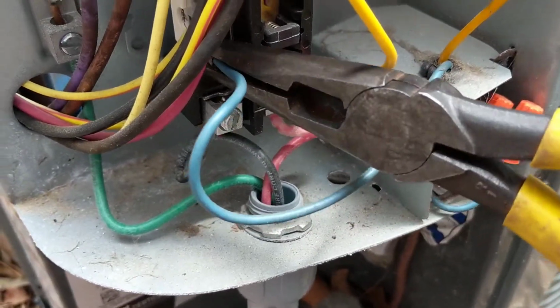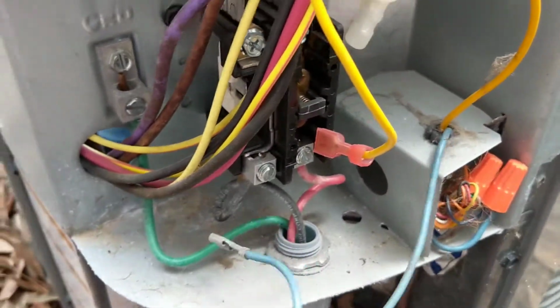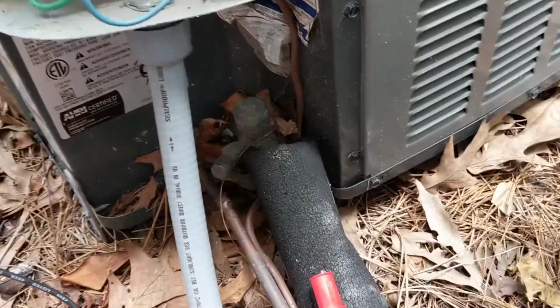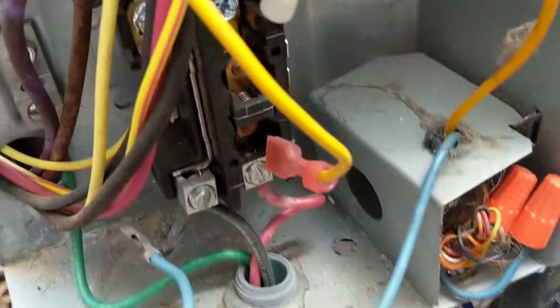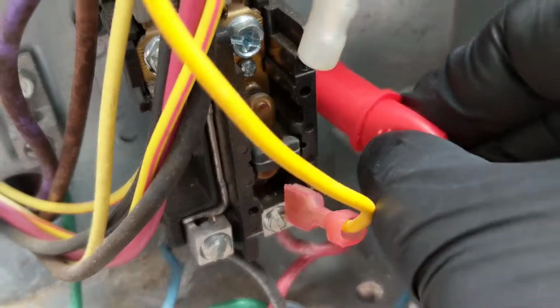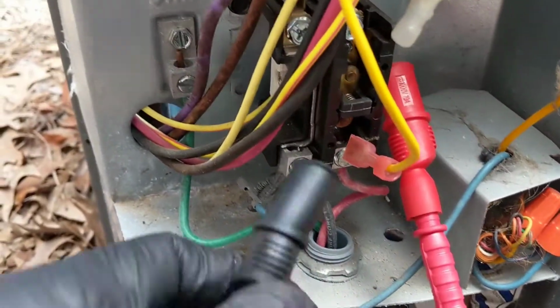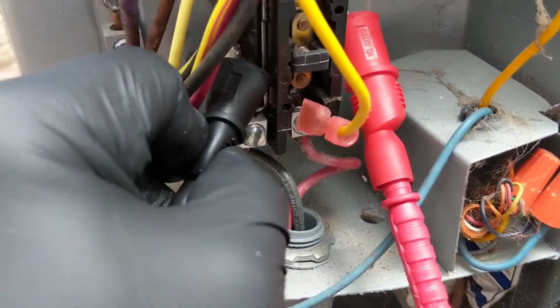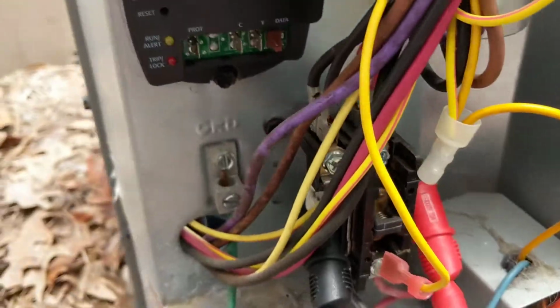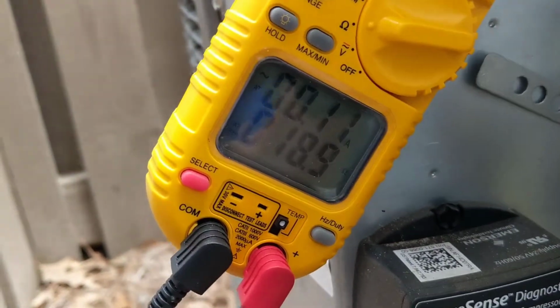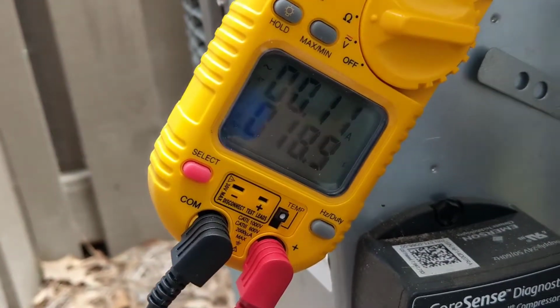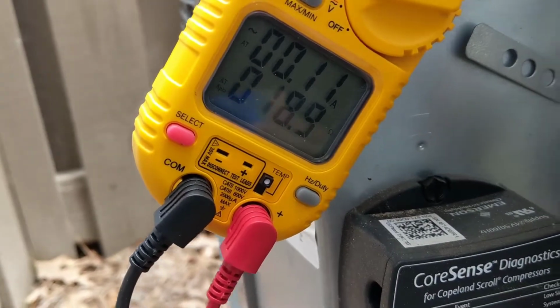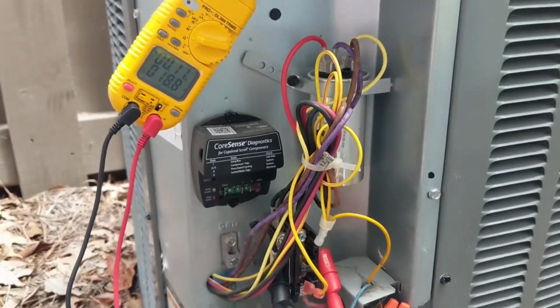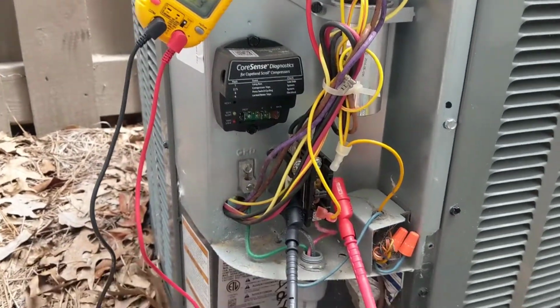Just pull your low voltage wires off and just ohm it out. Put one lead on one side and your other lead on the other. And it looks like we're getting about 18.9, so that looks good. So it looks like the contactor is good.